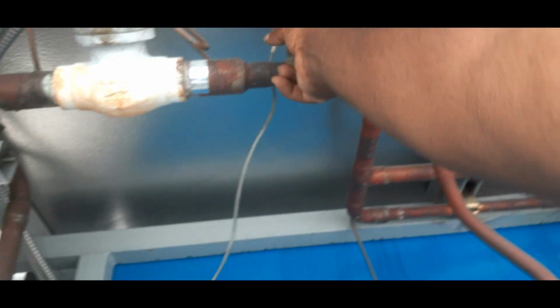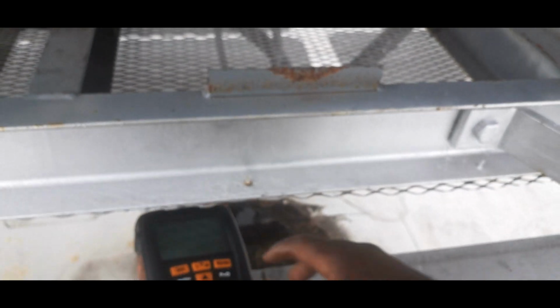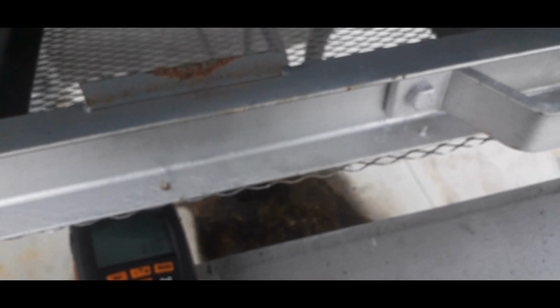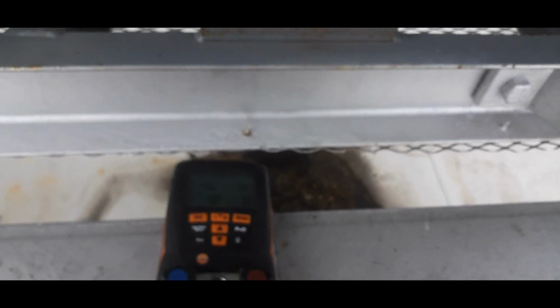This one is cold. This one's warm, but not too warm. Here's my transducer for my discharge. Get that to stay open. Open. Here's our transducer right here. Let's hook up my gauges. I always turn them on before I hook them up. I want to make sure that they're at 0 before I connect them. Alright, so 0, 0. Go ahead and hook this baby up.